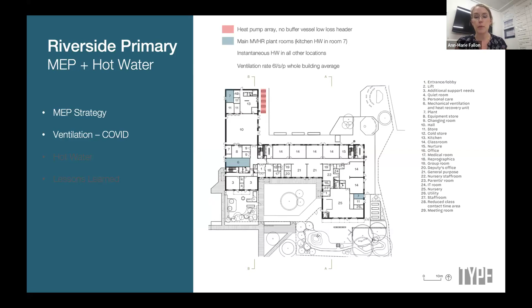Interestingly, the overall building ventilation rate for this project is 6 litres per second per person, whereas typically a school is designed for between 8 and 12 litres per second per person as a minimum. We're finding in Passive House projects, not just Riverside, that we're more than achieving indoor air quality requirements of 1,000 parts per million or less with that lower ventilation rate - still conserving energy. Chris can talk more about how we further optimize that later.